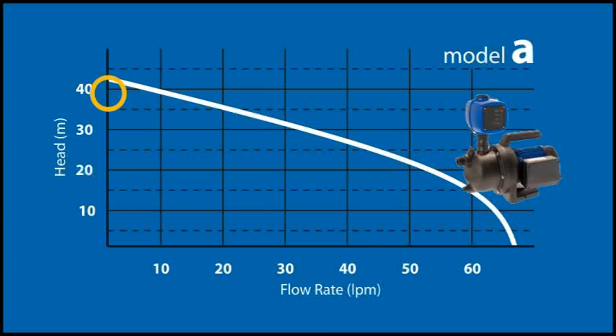On the graph, find 39 metres of head on the vertical axis, and run an imaginary line across the graph. At the point your line crosses the pump curve, draw another line directly down the graph to the flow rates along the horizontal axis. This is the flow rate your pump can deliver when working against the pressure you have calculated. Is the pump able to produce the flow rate required? In the case of model A, the answer is no.